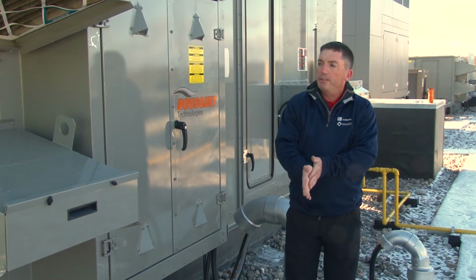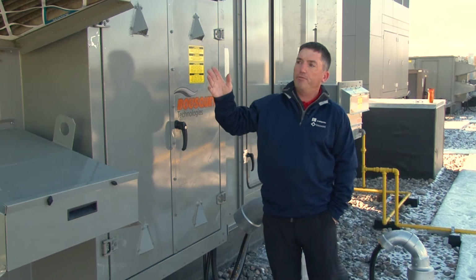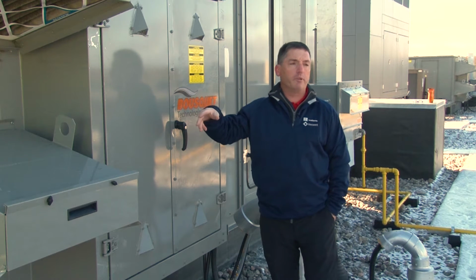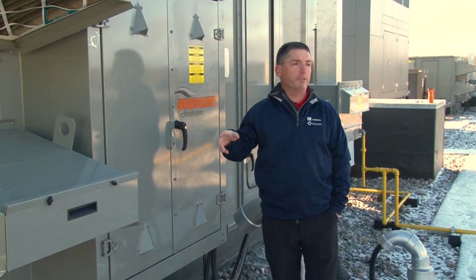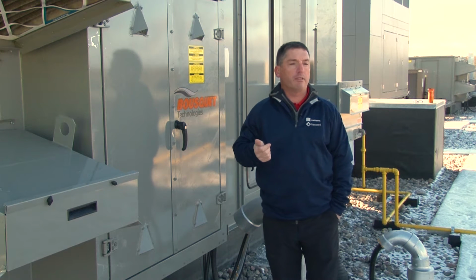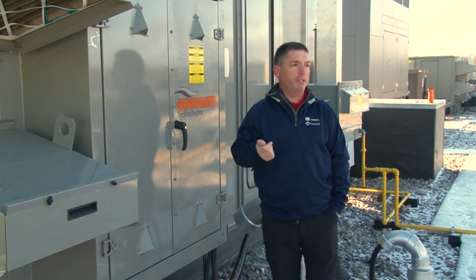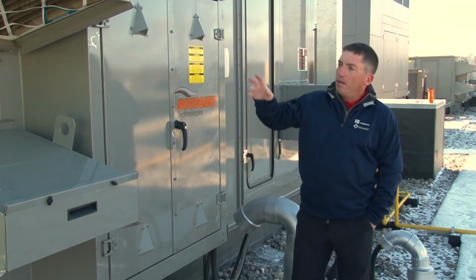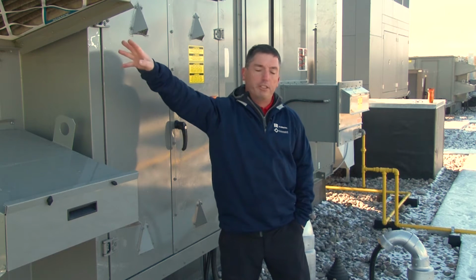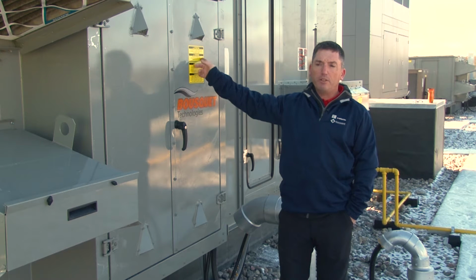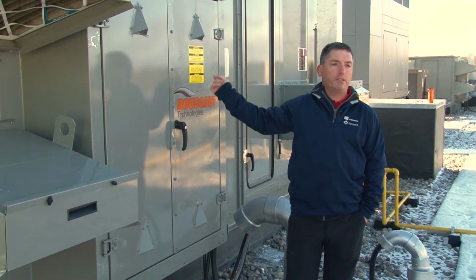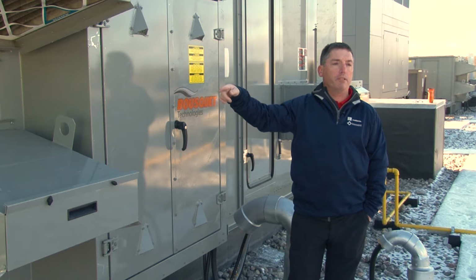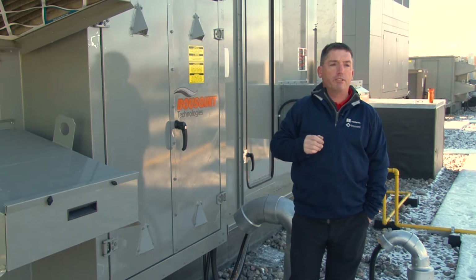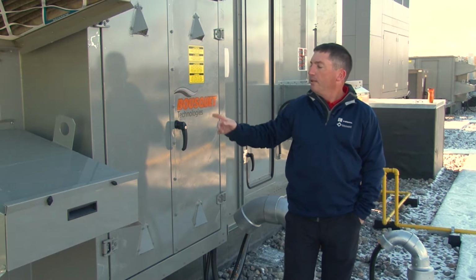Basic maintenance points that I'll cover: we have a handful of 2-inch disposable pleated filters that need to be looked at approximately 3 months a year. There's 2 here in the fresh air intake hoods, and then I'll show you on the other side of the unit where the exhaust air comes back from the building. There is approximately 6 filters inside there.